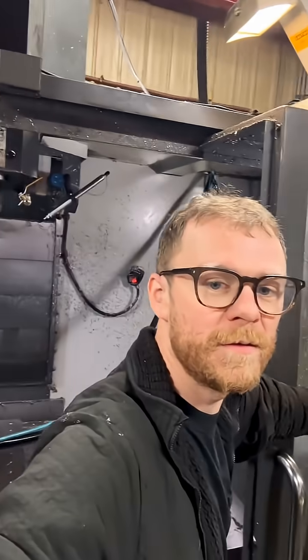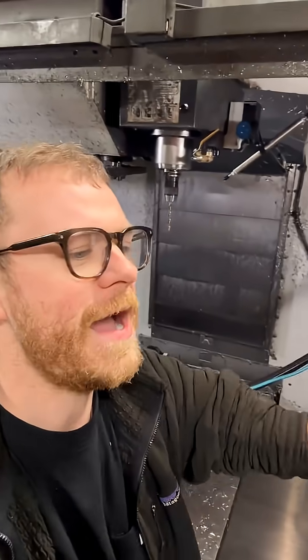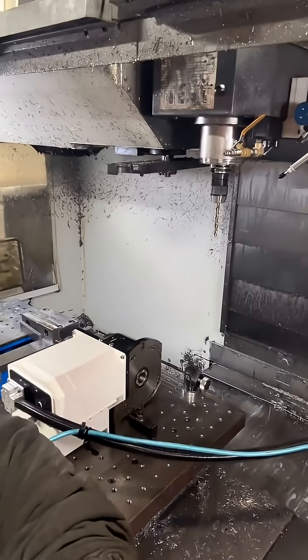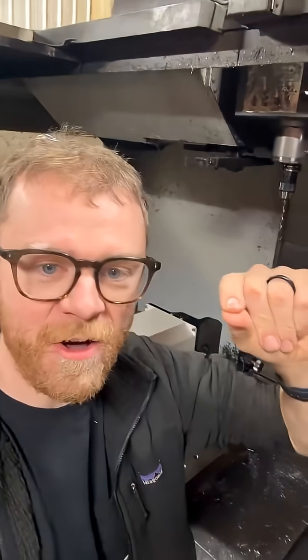Listen. A little bit of a click. Look right here — Z fell just two-tenths or so. Let's try it again. I just heard the braking engage and Z fell a little bit. Machine, if it's active, watch the head and listen. Boom. You could hear and see the head fall a little bit.